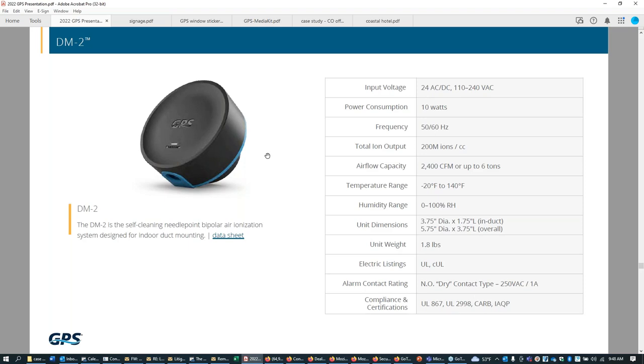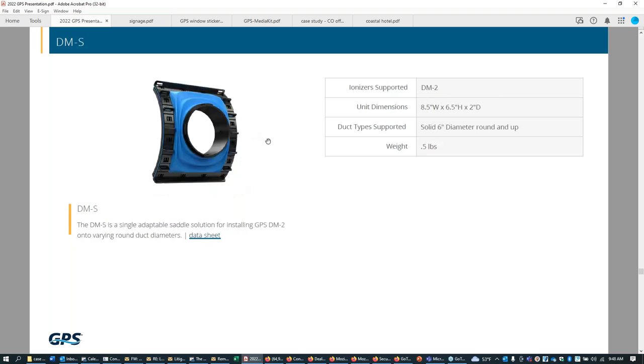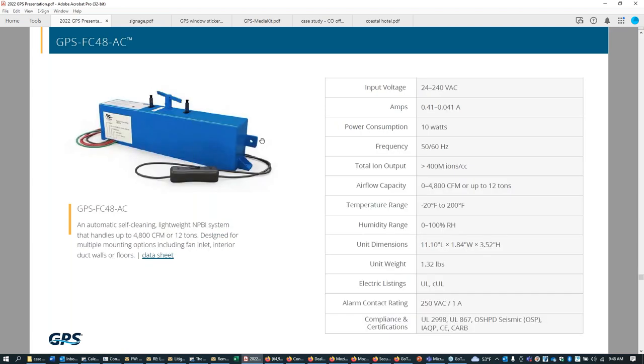If you are mounting this device into a rectangular duct, we've got a plastic bracket that this will attach to. It's a very simple installation. We wanted something to be able to adapt to round ducts of different sizes. And so if you've got a very large diameter duct that's round, you can use this with very little flex in it. This will flex all the way down to 6 inch in diameter. So that was very popular at the AHR show with the mechanical contractors, just making the installation even easier.